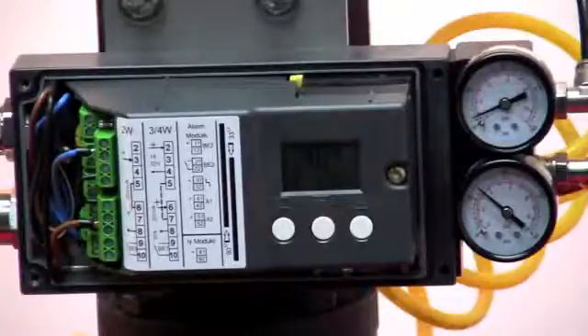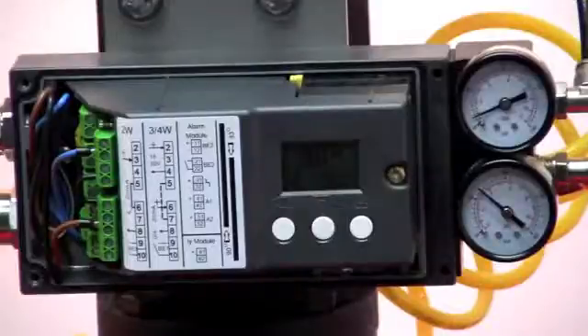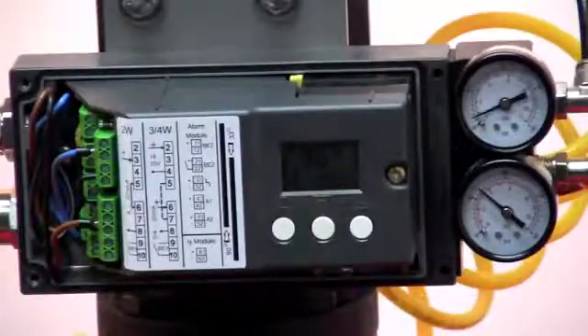If I select 33 degrees, I take my 32,000 bits of resolution and compress them down into 33 degrees rotation on the pot. I do this for short stroke valves and still get good resolution.